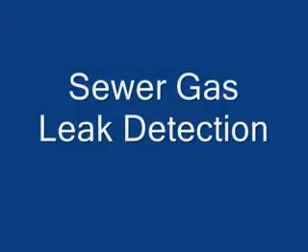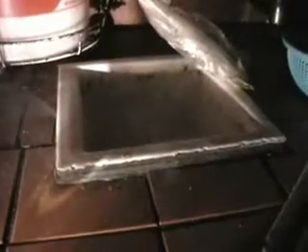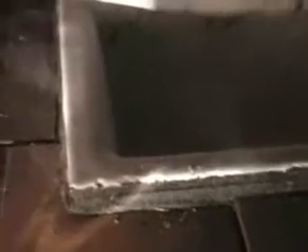This is a sewer gas smoke test to determine if there's any sewer gas leaking into the building. Here we have the kitchen staff complaining about the cook's alley back here really smelling strongly of sewer gas.